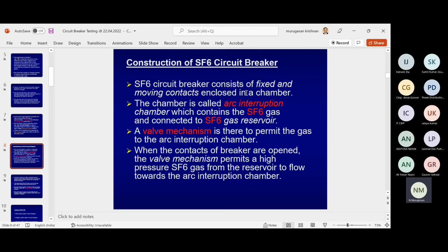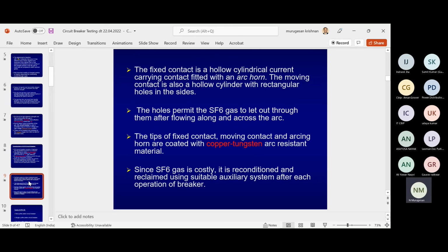Friends, an SF6 circuit breaker consists of a fixed and a moving contact enclosed in a chamber. Inside the chamber, you have SF6 gas. The fixed contact is a hollow cylindrical current carrying contact fitted with an arc horn. The moving contact is also a hollow cylinder with rectangular holes in the sides. The holes permit the SF6 gas to flow out through them after flowing along and across the arc. The tip of the fixed contact, the moving contact, and the arcing horns are coated with copper tungsten, an arc resistant material. SF6 is costly, so it is recommended to reclaim it using a suitable auxiliary system after each operation of the circuit breaker.